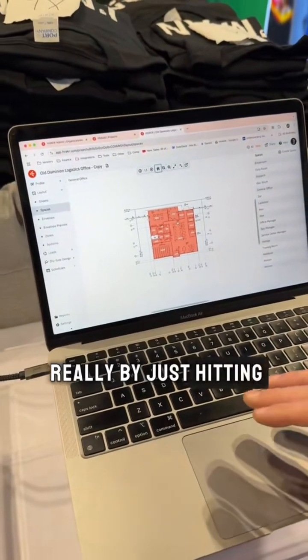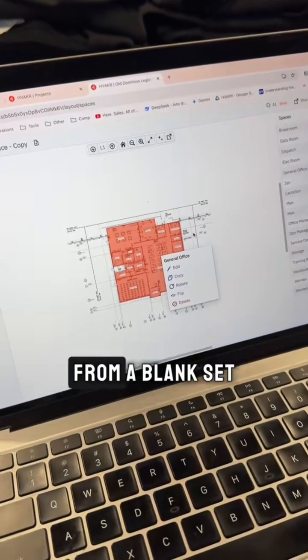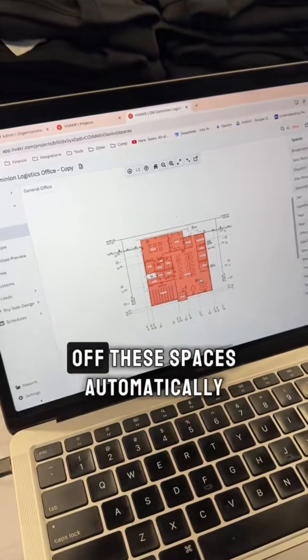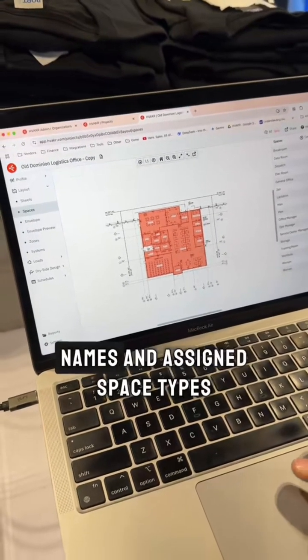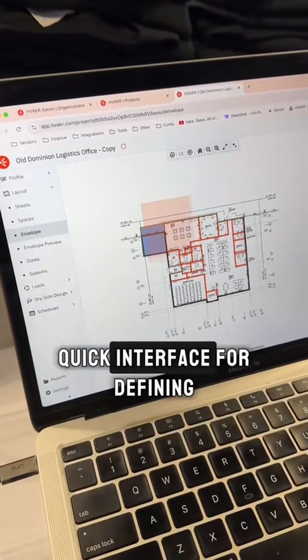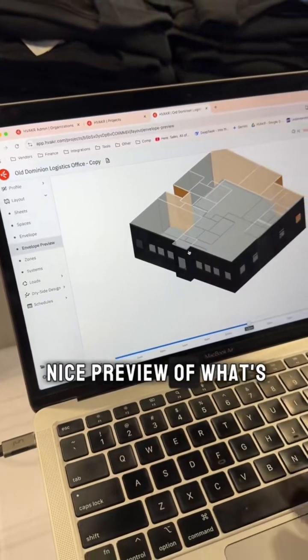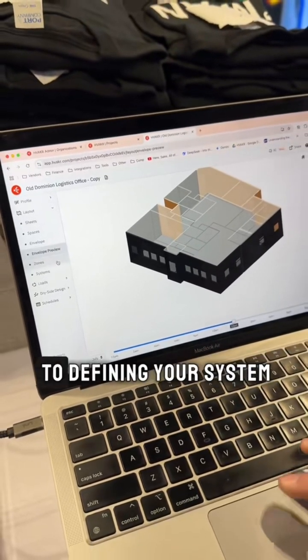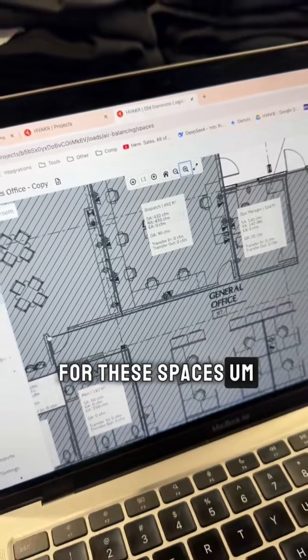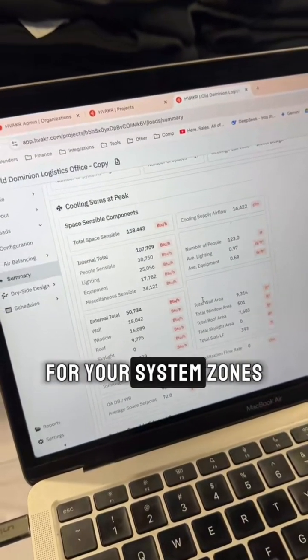We've added a really cool feature — just by hitting that button. This is the AI part. We just released a feature where from a blank set of floor plans, you hit this magic AI button and it will read the PDF and take off these spaces automatically. It will even pick up space names and assign space types. From there, you jump to your envelope — a really quick interface for defining your exterior roof and slab — and you get a nice preview of what's going on. There are more steps to defining your system, like zoning, so you can see all the airflows required for the spaces. After that, you get a loads report with all the typical values you want to see for your system, zones, or spaces.